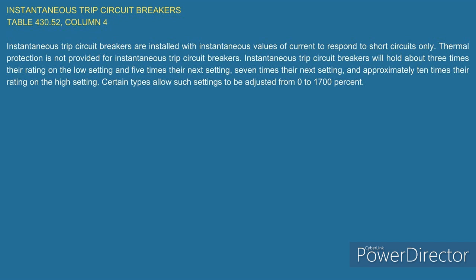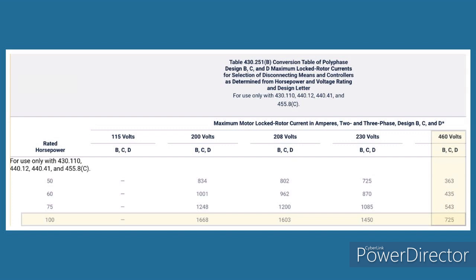And these certain types can be adjusted from what? 0 to 1,700%. And you can pick that up in 430.52C3, which tells you about that 1,100% up to 1,700%, the minimum and the maximum. Is this like a motor overload device? Yes. And watch this. You're going to love this. Now watch. I'll come right back to this.